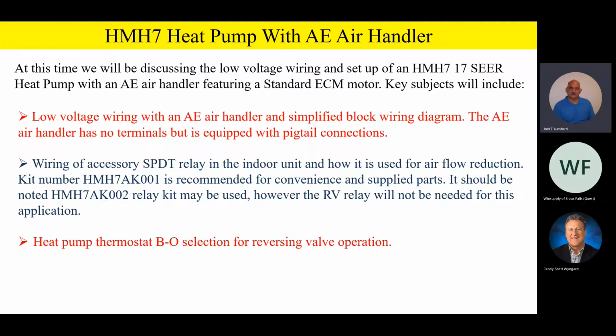So at this time, fellas, we're going to go ahead and talk about hooking this thing up. We're going to be looking at some low voltage wiring and setup of the HMH7 SEER heat pump with an AE air handler, which is going to feature just a plain high efficiency ECM motor. Now, at this time, we're also going to be looking at a low voltage block wiring diagram, and we're going to literally go wire for wire from the thermostat to the indoor unit to the outdoor unit.